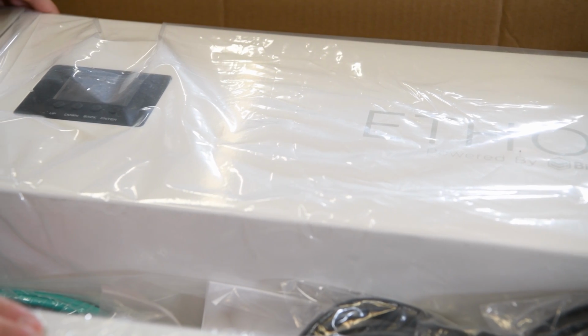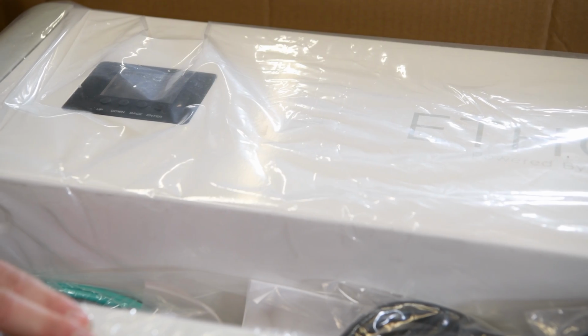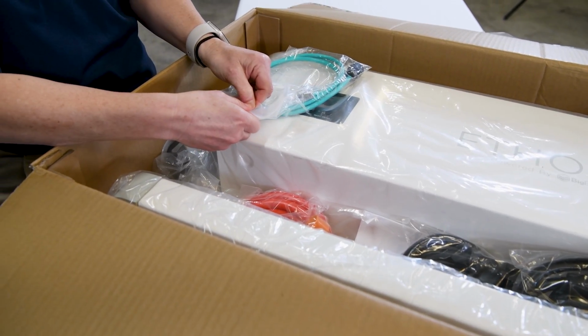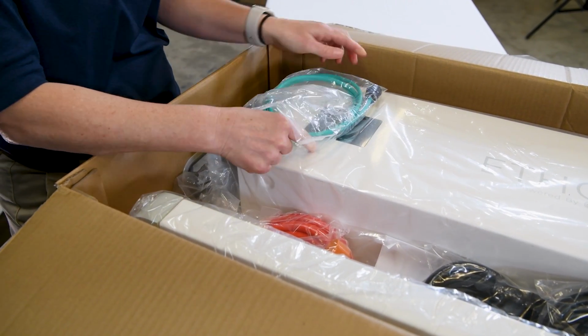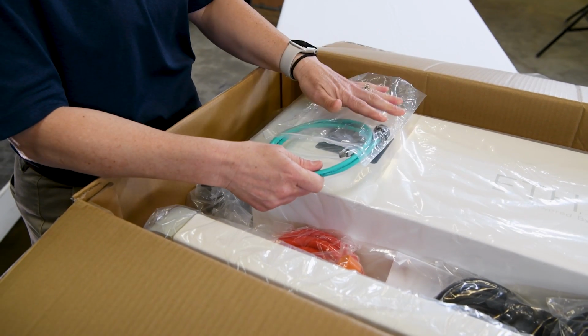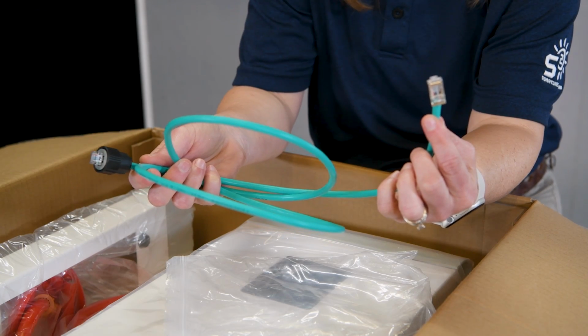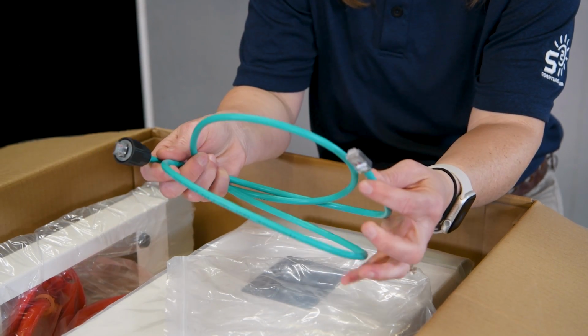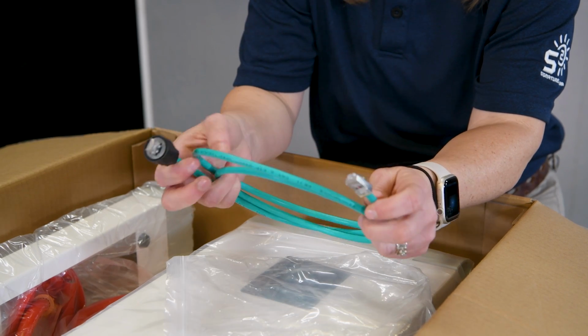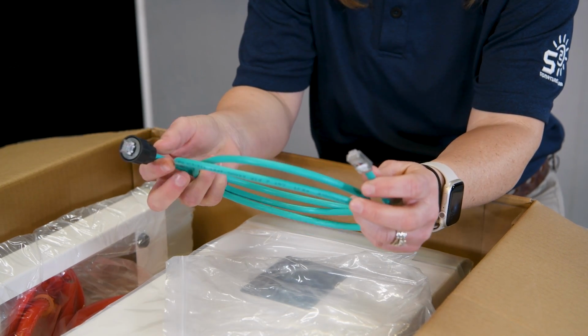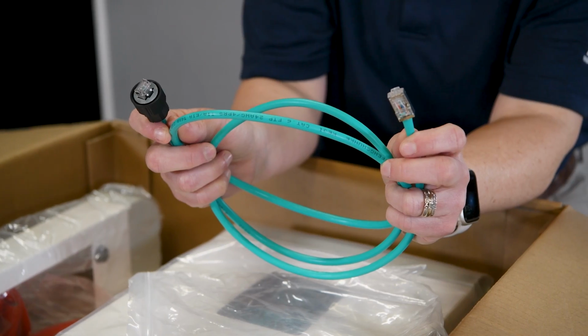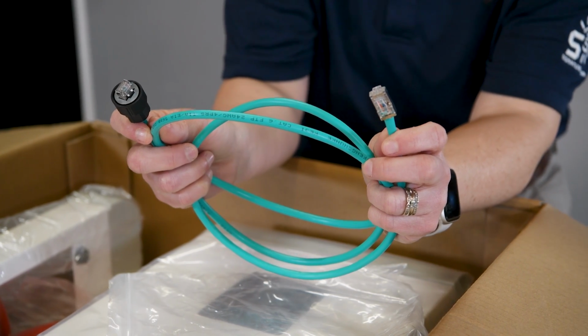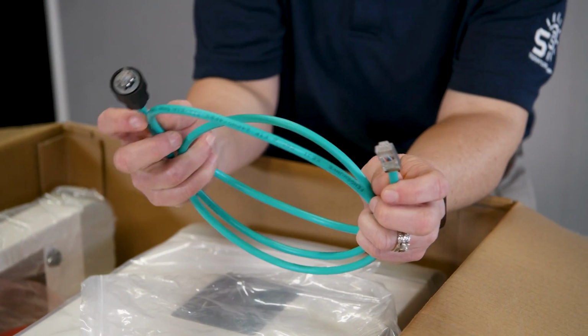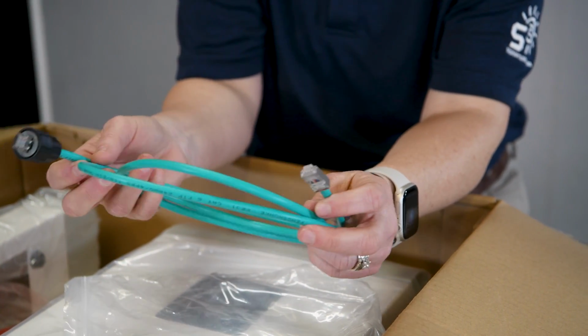Before we pull out these big items, let's take a look at the cables that come included in this box. Take note that each of these cables are designed to go straight from the controller to the inverter. First, we have the controller to the inverter communication cable. Notice the plain RJ45 connector on this end will go straight into the communications port in your inverter, and the other end will screw securely into the communications port of the controller box.